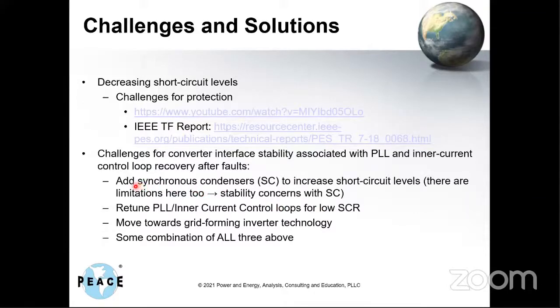So one of the things that is actually being done in systems around the world is you introduce synchronous condensers to increase the short circuit strength in a region where there's a high penetration of CIG. But there is a limitation to that as well. If you put in too many synchronous condensers, remember they are synchronous machines, you may start to get rotor angle stability issues with those and have to find ways to mitigate that. So there's a balance there. You can't just keep putting in more and more synchronous condensers.